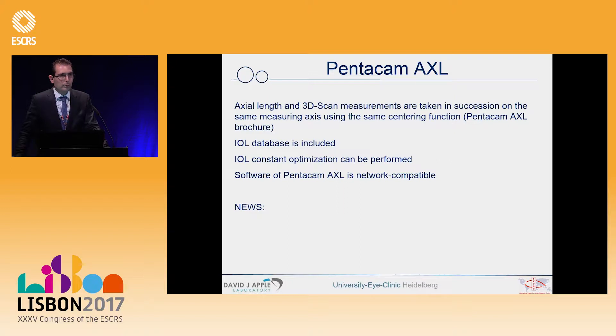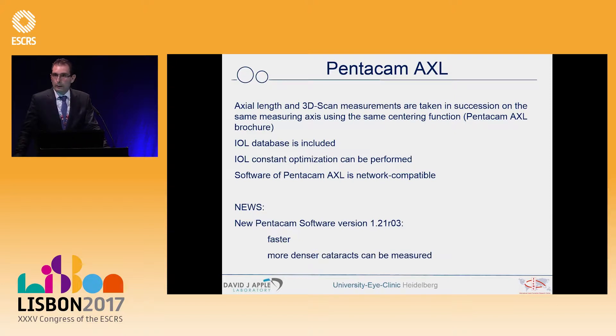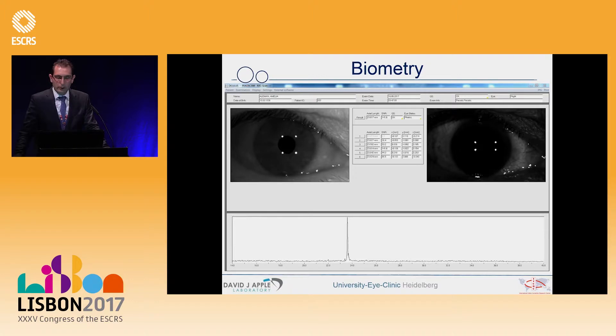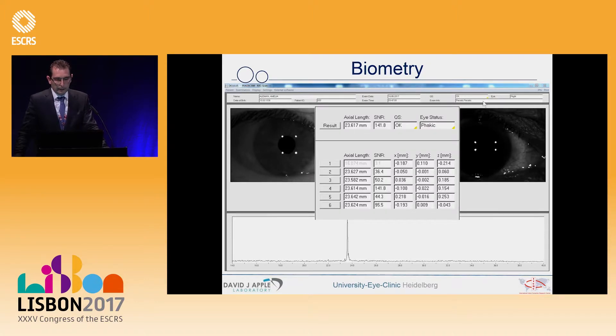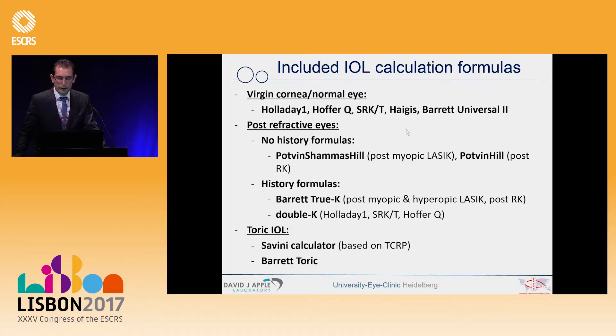It's network compatible, and the news for the new software is that it's faster. The scan process is very fast, and even denser cataracts can be measured. In the biometry setup, after taking six average axial length measurements, the intelligent software picks out every outlier statistically before calculating the real axial lengths dependent on the signal-to-noise ratio, which should be very high to achieve a perfect axial length measurement.